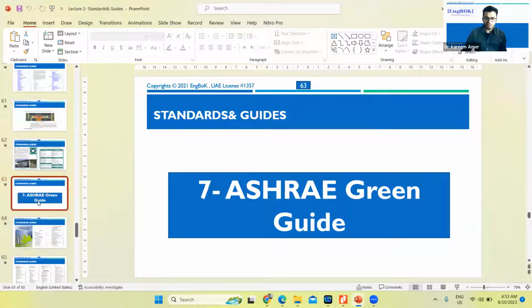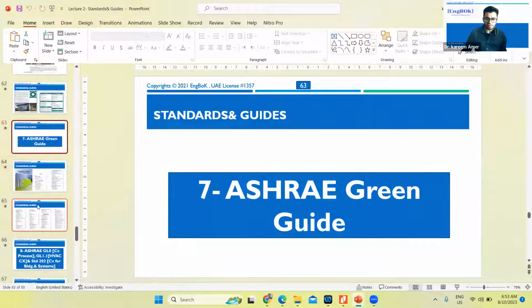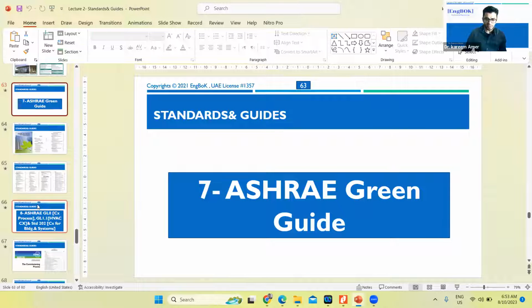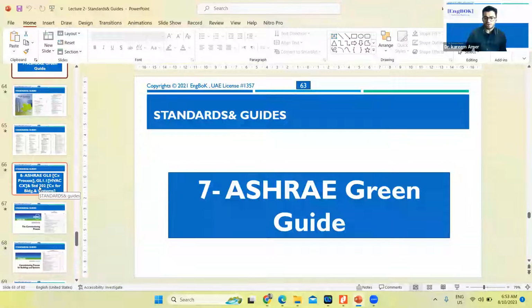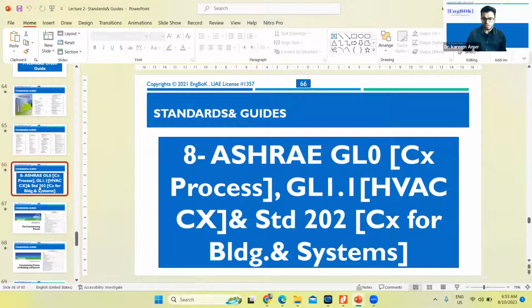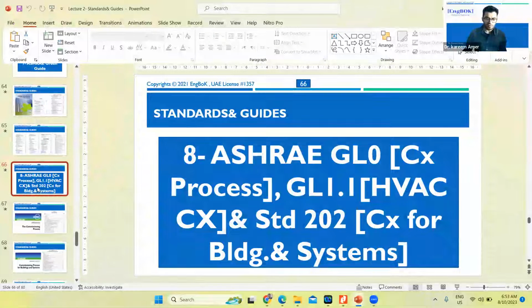We're also going to cover the ASHRAE Green Guide, the main sections and contents, since it's the main guide for green building. And the ASHRAE standards and guides for the commissioning process, either Guideline 0 for the commissioning process, or 1.1 for HVAC commissioning process, or Standard 202 for commissioning of building systems.